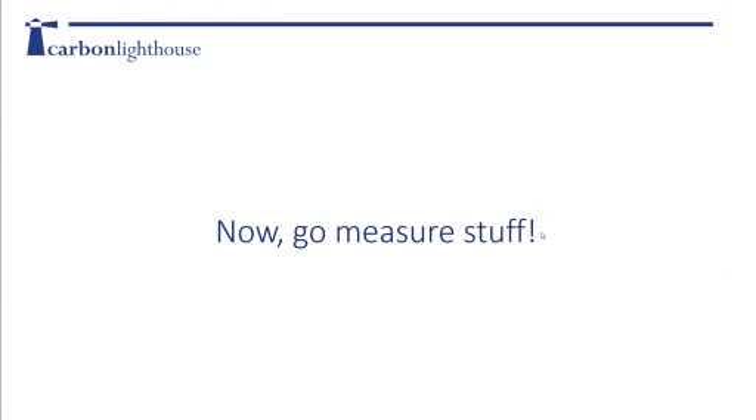How is the best way to measure floor temperature? If this is about a concrete floor, I would get an external temperature sensor, put some insulation over it, and secure it to the floor - you'll get a pretty accurate measurement. Another way is a simple spot measurement with an IR gun, depending on whether you need data over time or just a current reading.